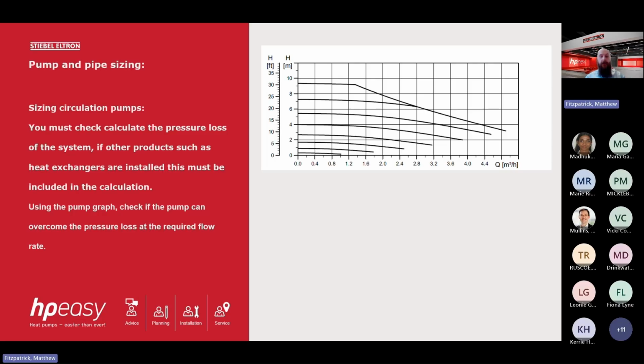Now, increasing the pipe size, so say for example you have 28 mil flow and returns on the primary to the air source heat pump and the buffer cylinder. If the heat pump is 20 meters away from the buffer cylinder and you have a high pressure loss in this primary circuit and may require a larger pump, you could increase the pipe diameter to 35 mil. As there's a bigger pipe diameter, there's less pressure loss, which means you may not need to oversize the circulation pump. So there's two aspects. The pipe sizing is crucial to the pump sizing and vice versa.